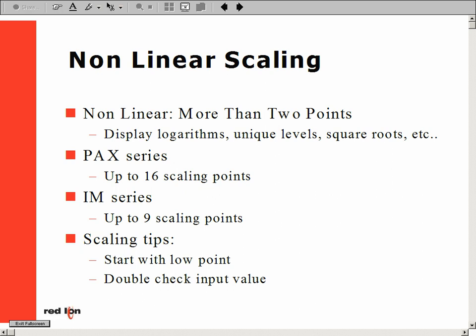Linear scaling is set up like two parallel lines, with a high point and a low point. Non-linear scaling may have multiple points to fine-tune your desired reading. In our PAX series of meters, you may scale as high as 16 points. For our IM series of meters, you may scale up to nine separate points.